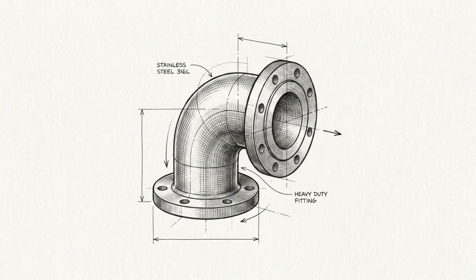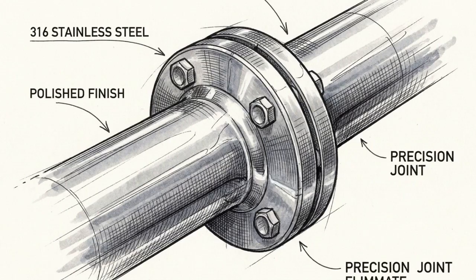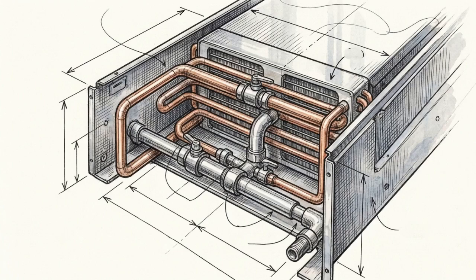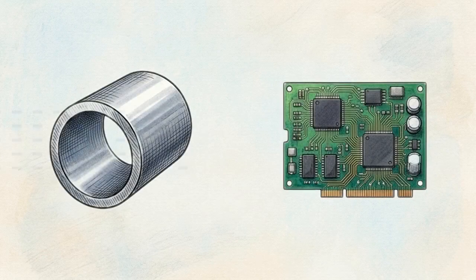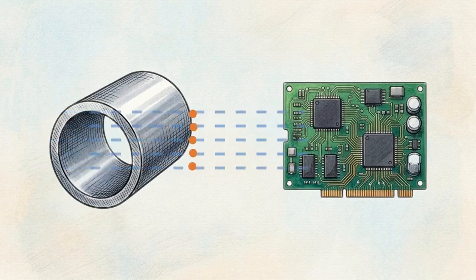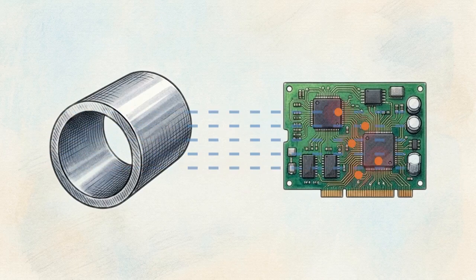The internal fluid loop adheres to strict material constraints. It requires marine-grade 316 stainless steel, with zero brazed copper, zinc, or brass permitted anywhere in the fluid path. These restrictions eliminate galvanic corrosion. If lesser metals were used, copper ions could migrate through the coolant and deposit directly onto the server logic boards, causing systemic component failure. The CDU also executes precise dew point control.